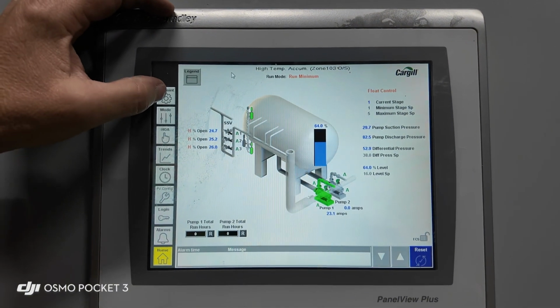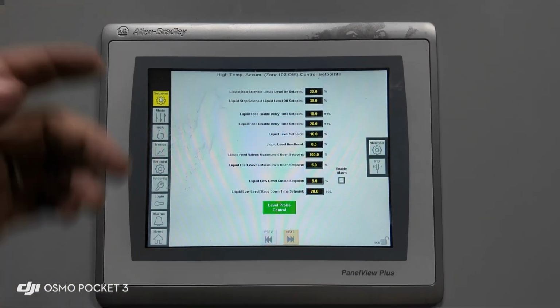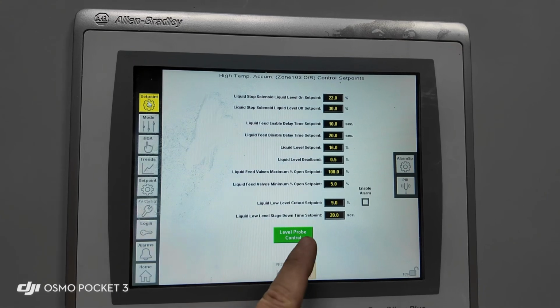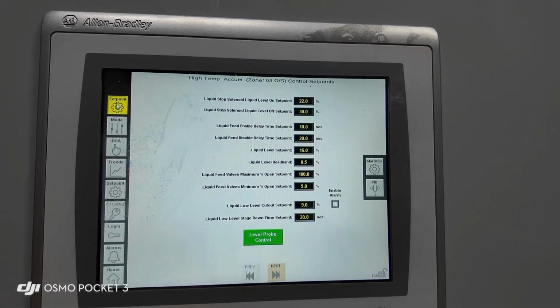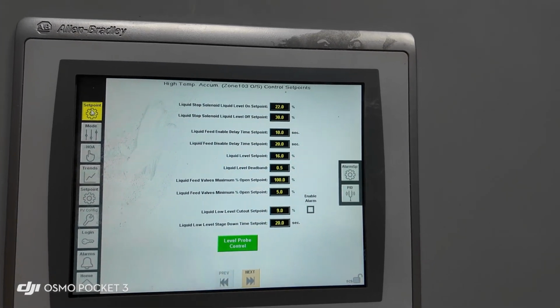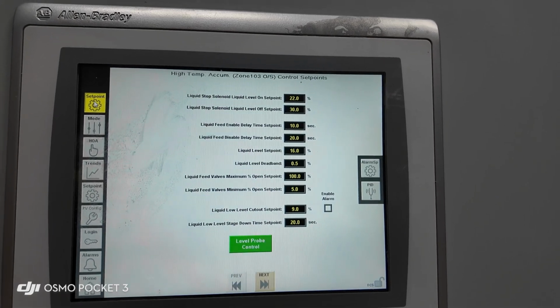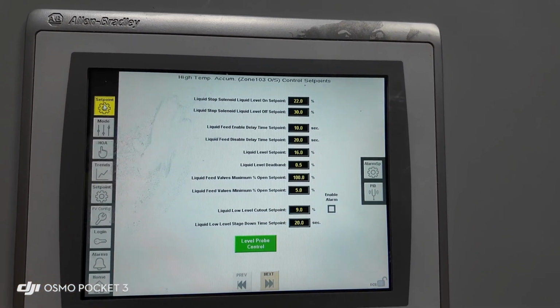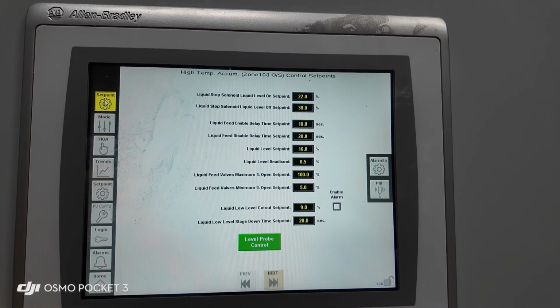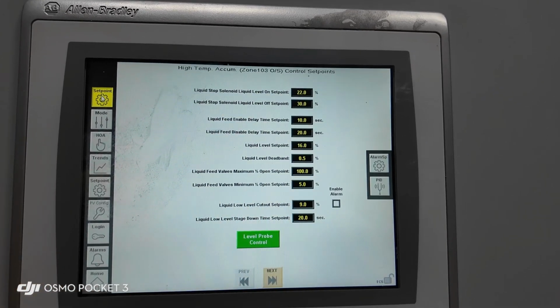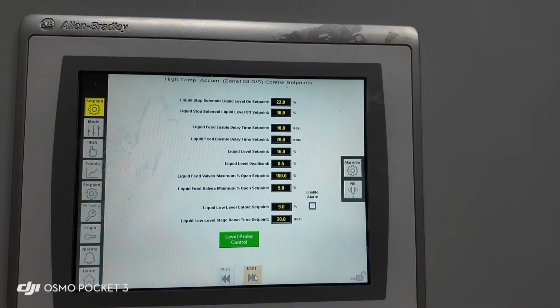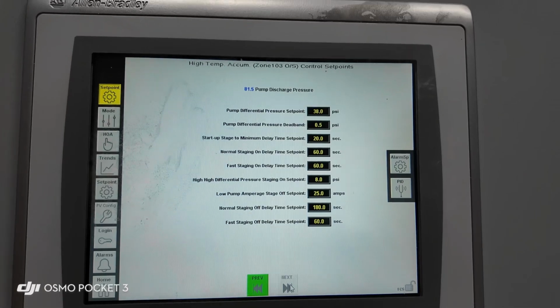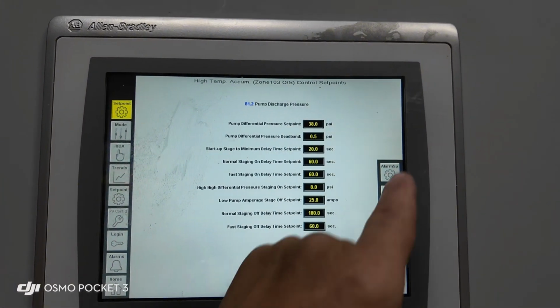We can then start from the top down. We can go to set points, which these are all of our set points. This is also where we switch it from level probe control to float control. What you see is what you get. If I were to push that button right now, it would go back to level probe control from its current float control. There's a next at the bottom, takes us to the next screen.